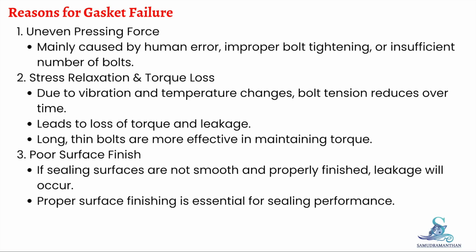Now, even the best gasket can fail if the installation is improper. Let us understand the major causes of failure. Uneven distributed pressing force, often caused by human error, uneven bolt tightening, or insufficient number of bolts. This results in leakage due to poor sealing pressure.